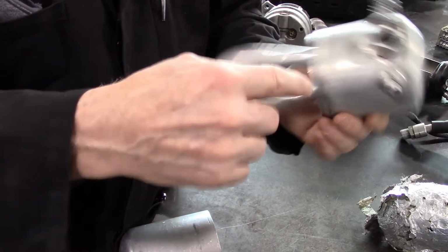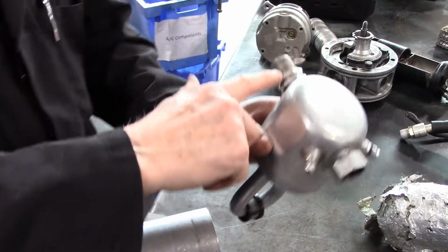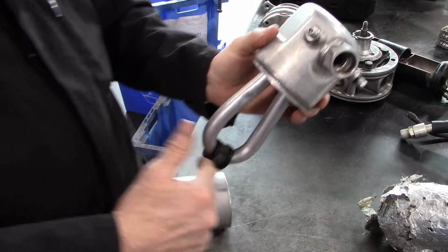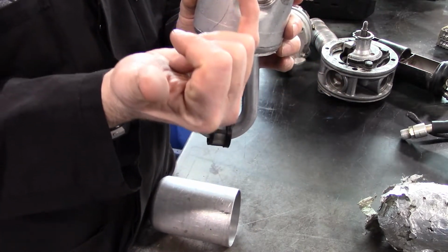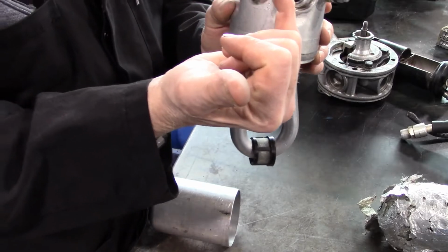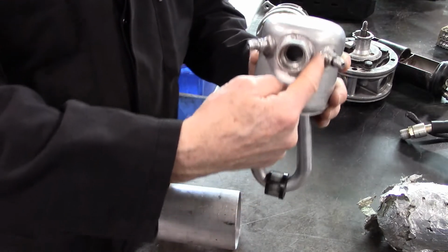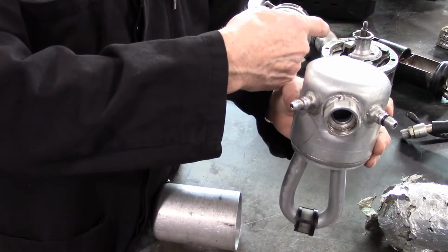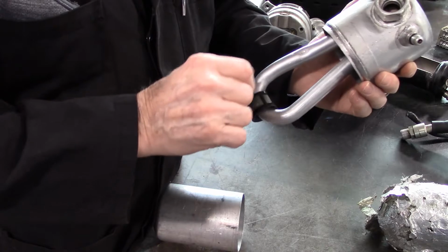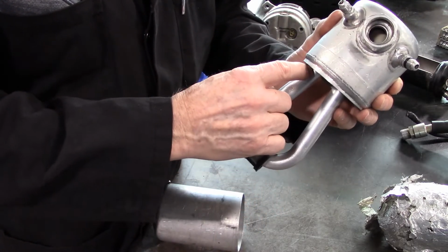One tube is connected to my outlet, and it comes in and down and around and up. Think of it like a straw where the end of the straw is sticking to the top. That is to ensure that it pulls gas from the top of the accumulator down through and to my outlet. We do not want any liquid refrigerant going in here.